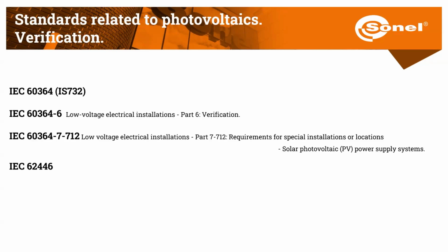Fortunately, for those doing photovoltaic installation inspection, only two standards are truly important. This is IEC 60364, known as IS 732 in India, and IEC 62446 as well. From this, the key sections are part 6 of IEC 60364 and section 712 in part 7 of the same standard. For IEC 62446, we need to focus on part 1 and part 2.